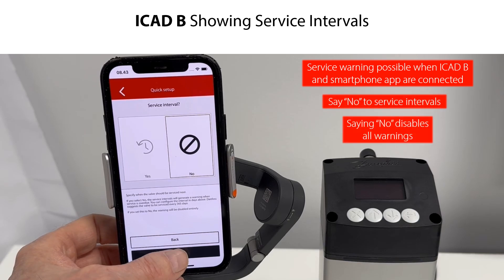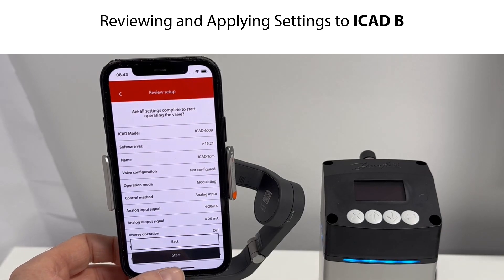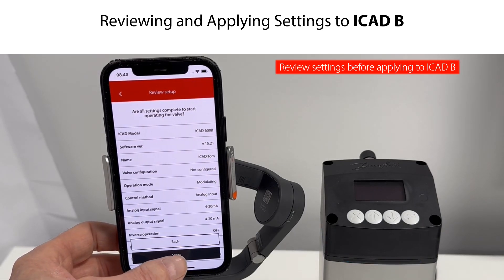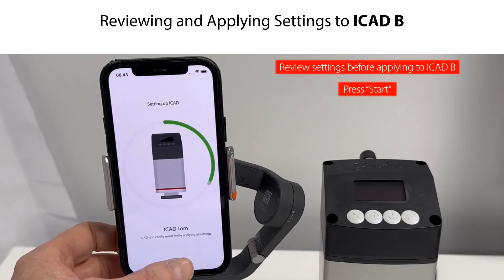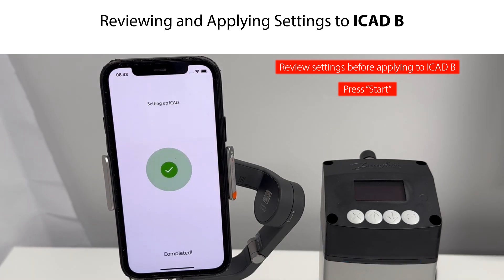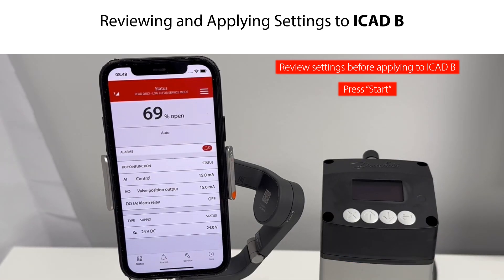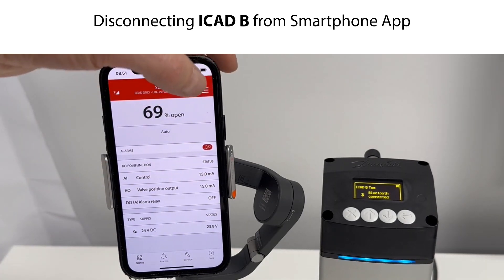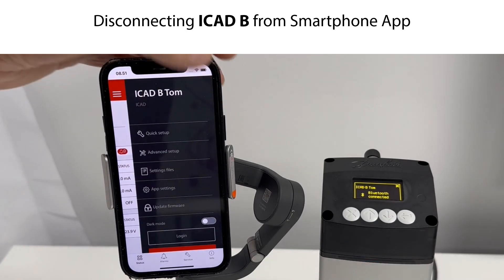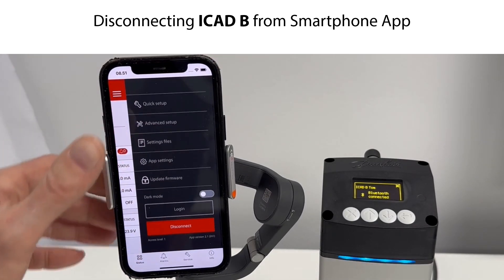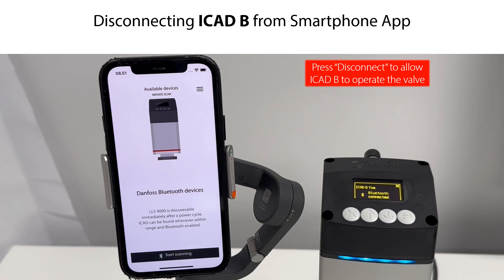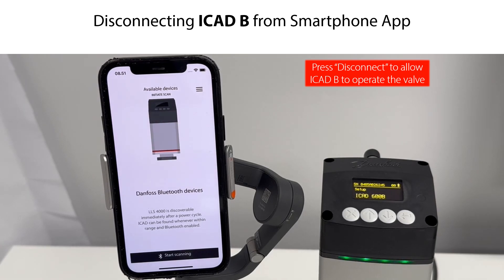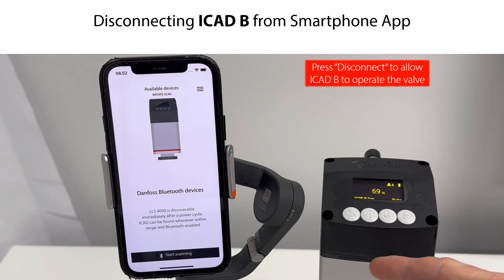Please note that if you say No to the service intervals, then the warnings will be completely disabled. You now get an overview of the selected settings, which you can review. Press Start to confirm and apply the settings to the ICAD-B. This brings you to the ICAD-B smartphone home screen. If you have completed the ICAD-B setup and configuration, press the menu icon in the top right corner and press Disconnect. This allows the ICAD-B to operate the valve according to the given settings.